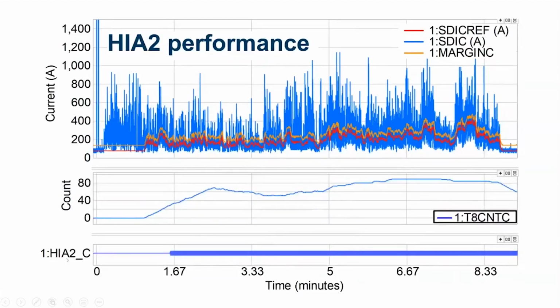This is what the alarming bit looks like, HIA2. You can see it's the exact same thing. I have the SDI reference, I have the margin, and I have the actual SDI. So how does the alarming counter assert? The alarming counter also looks at the deviation from the margin, but it looks at smaller values of deviation over a larger amount of time. That's why you see the counter constantly increasing for this one. The counter value is also sufficiently high. It's not increasing abruptly, but gradually. And that's why we see that the alarm bit was constantly asserted for this fault.